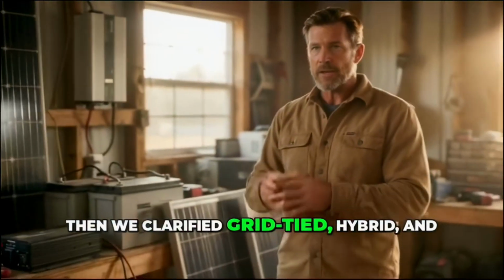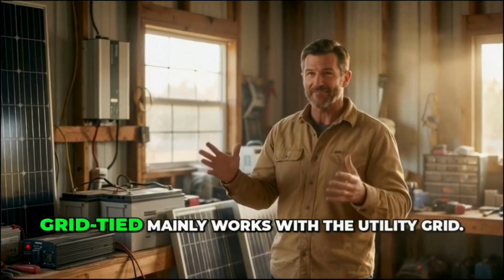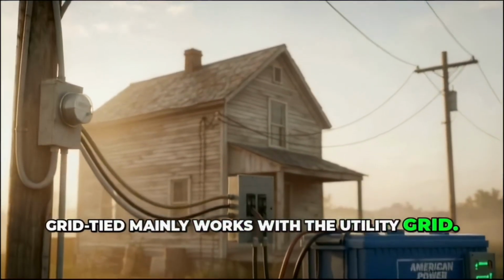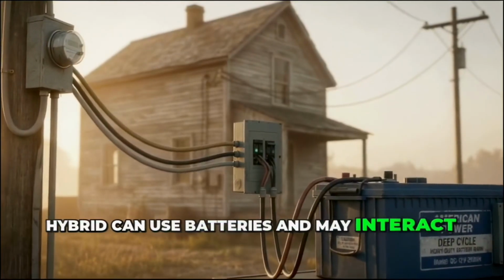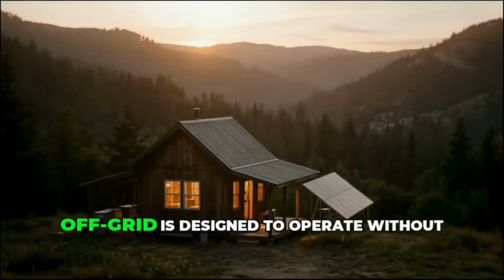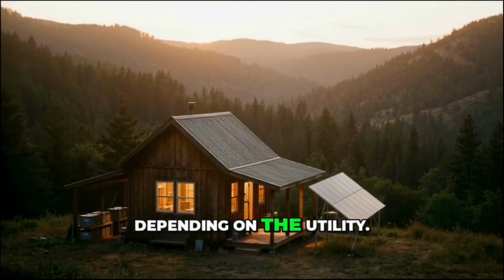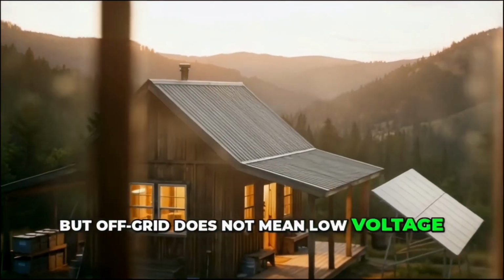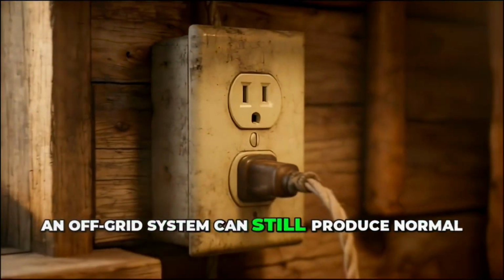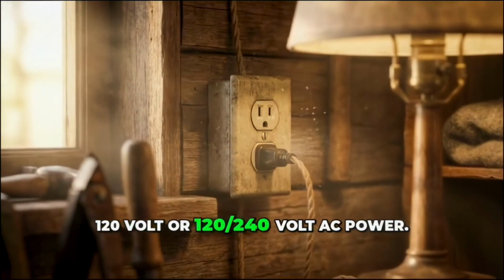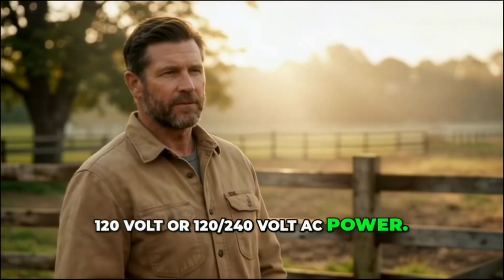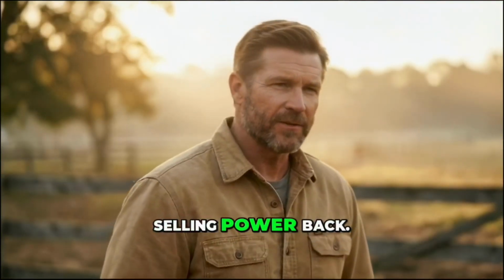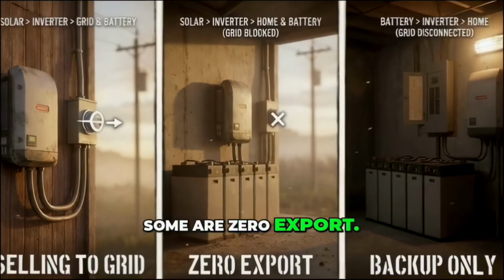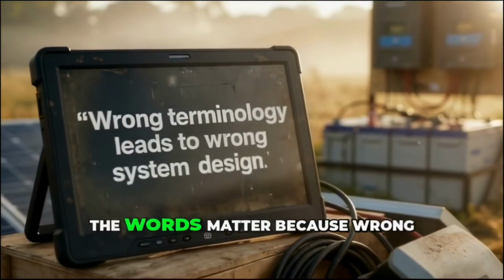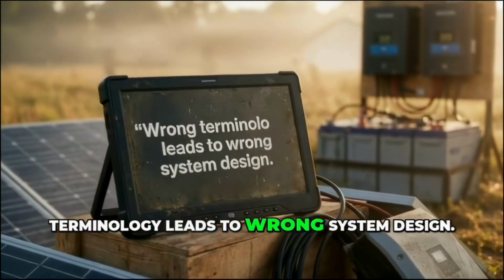Then we clarified grid-tied, hybrid, and off-grid systems. Grid-tied mainly works with the utility grid. Hybrid can use batteries and may interact with the grid depending on setup. Off-grid is designed to operate without depending on the utility. But off-grid does not mean low voltage only. An off-grid system can still produce normal 120-volt or 120/240-volt AC power. And hybrid does not automatically mean selling power back. Some hybrid systems sell, some do not. Some are zero export. Some are backup only. The words matter because wrong terminology leads to wrong system design.